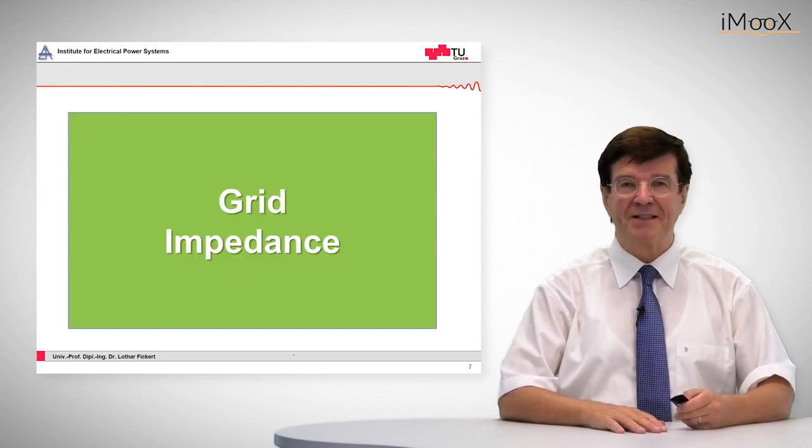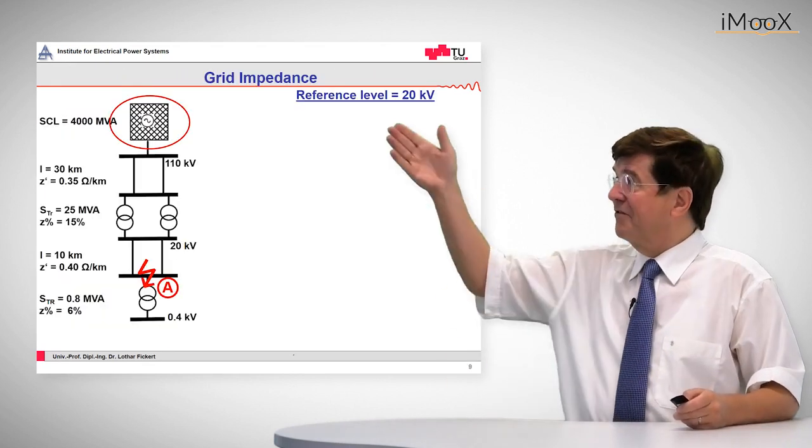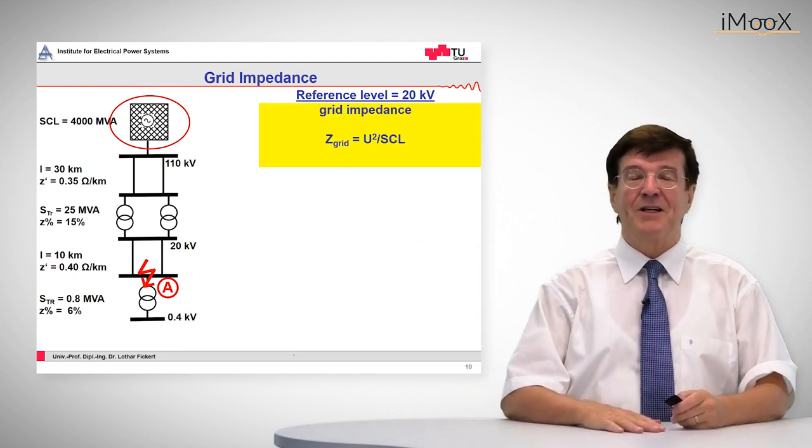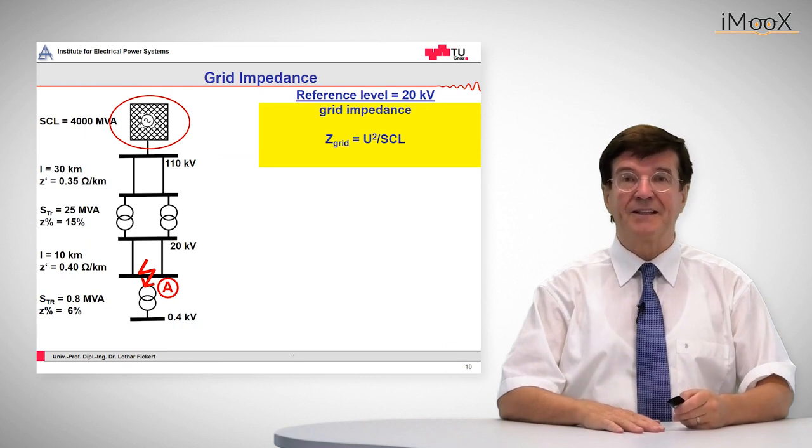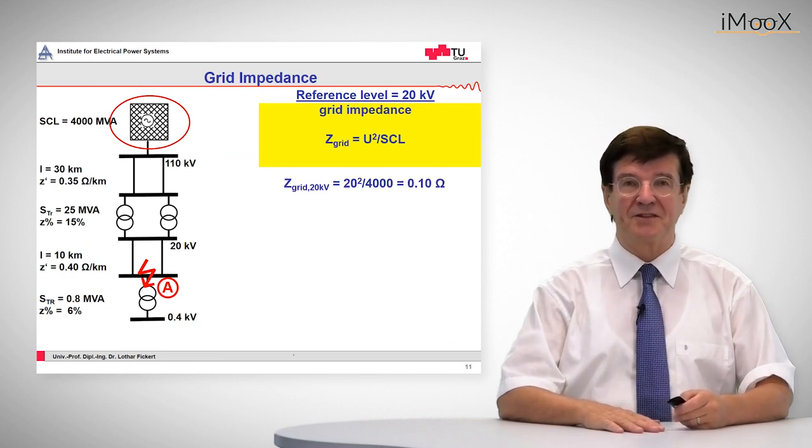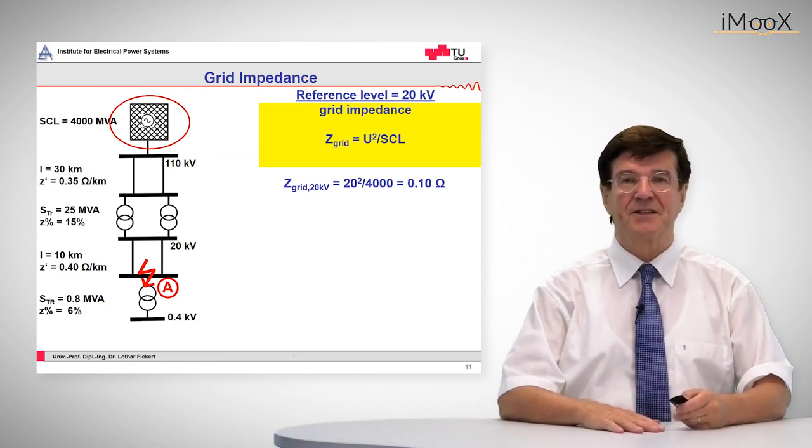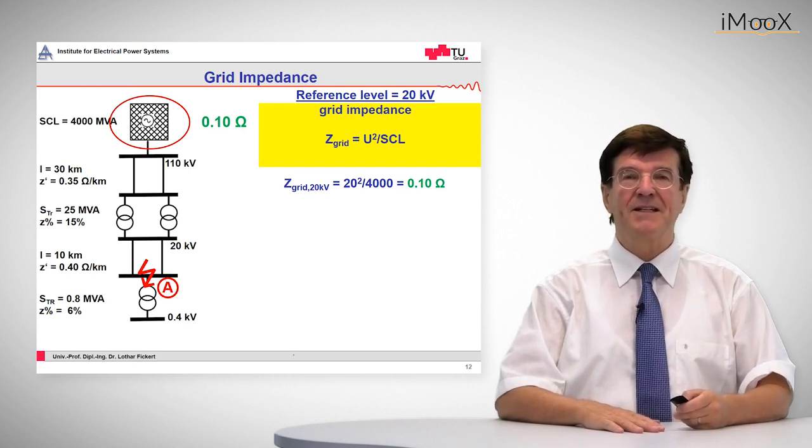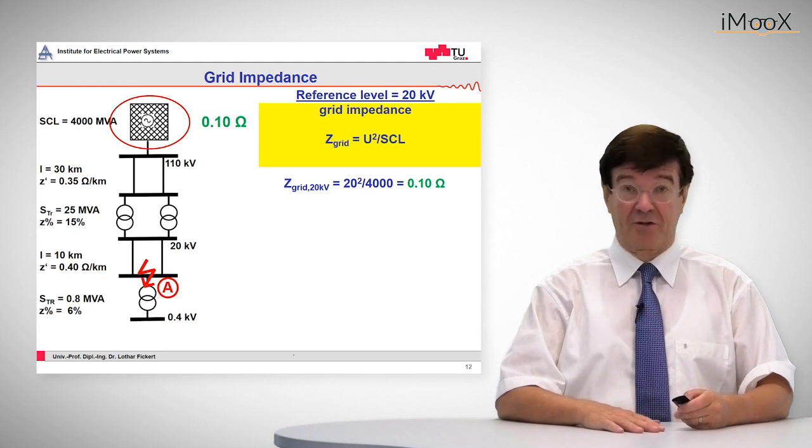Let's start with the grid impedance. The grid impedance is given by the following formula: it is U squared divided by the short circuit level, and in this case we obtain a value of 0.10 ohms. So these 0.10 ohms are the result for the grid impedance on the 20 kV voltage level.